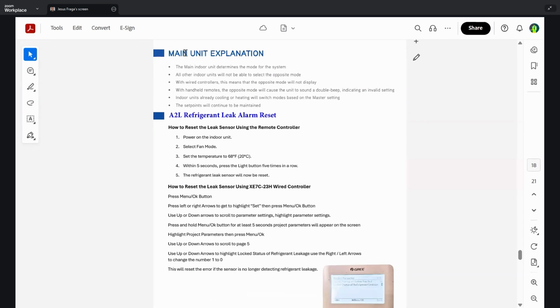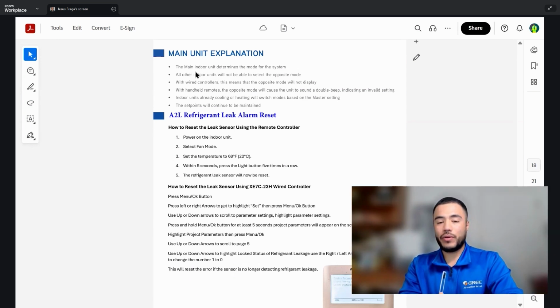So as I stated earlier, here's an explanation on what a main unit designation actually means. There's one wired controller that's going to be designated as the main indoor unit. We need to not confuse this with main indoor wired controller. The main difference is each system that has a wired controller will be designated as a main wired controller, but there's only one main indoor unit.